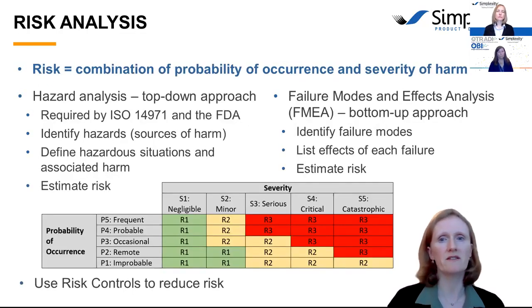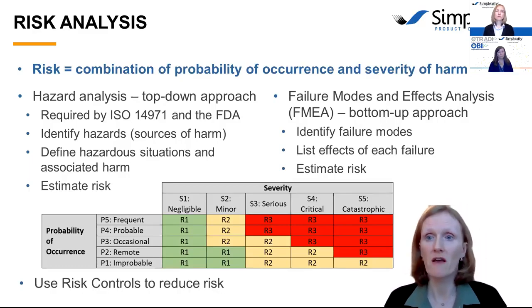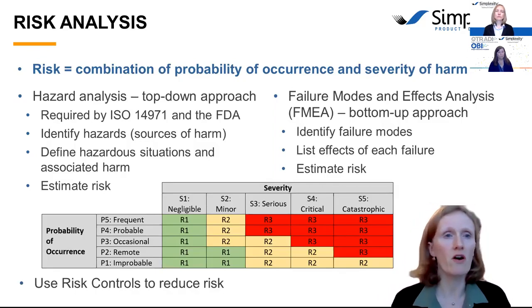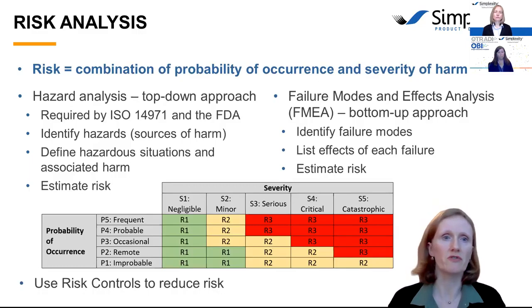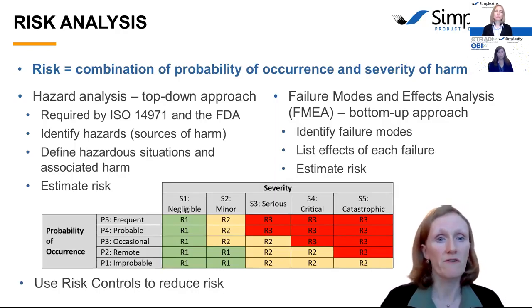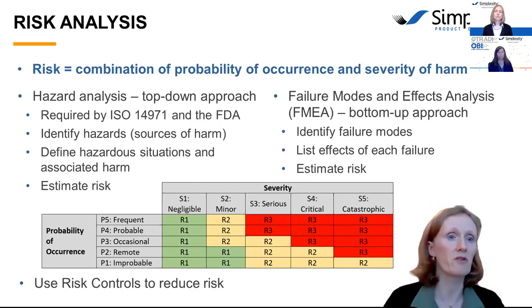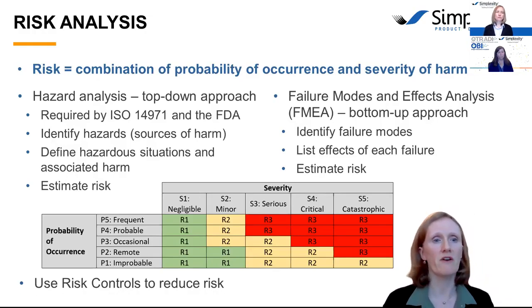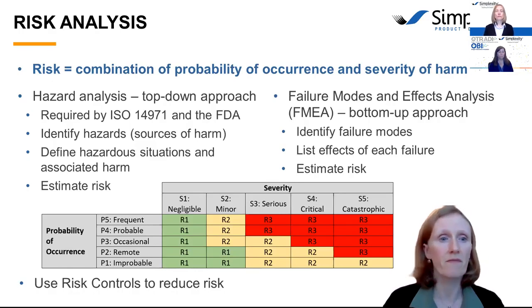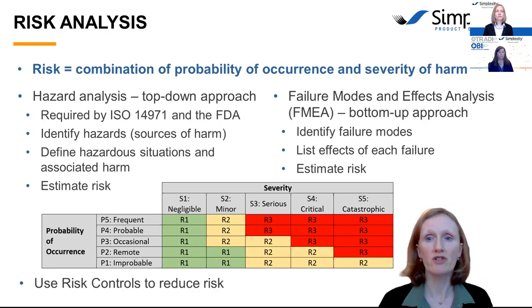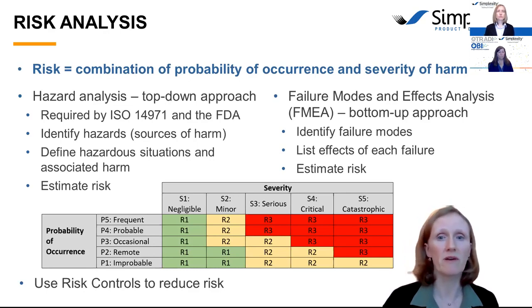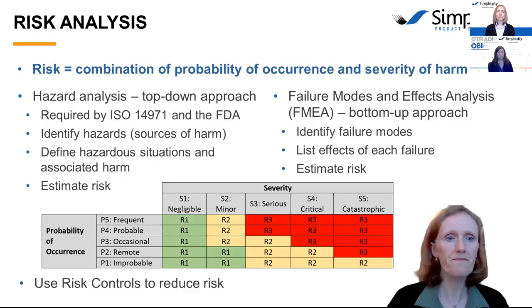So, a risk analysis. Risk is the combination of the probability of occurrence and the severity of harm. So you're asking, how often does a failure happen, and how serious are the consequences when it does? There are many different tools for doing risk analysis, but two of the most well-known are a hazard analysis, which is a top-down approach, and a failure modes and effects analysis, or FMEA, which is a bottoms-up approach. In a hazard analysis, you start by identifying the hazards, at the top level. What are the sources of harm? Then you take those and define a hazardous situation where you expose someone to potential harm, and what the associated harm is. And then from there, you can estimate the risk of that harm.